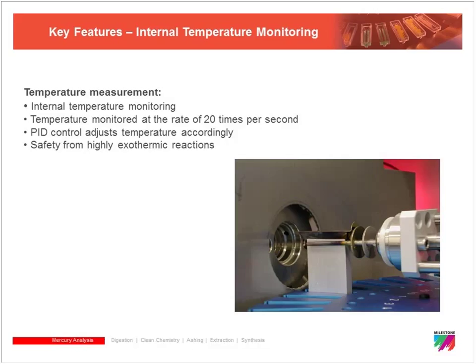So you can predefine this feature prior to your analysis, but generally for the most part you'll only need one or two methods, where you have one method for all of your samples, and then if you are running some very high oil or fat samples, you would have another one that allows you to extend out your heating cycle. This can all be done on the front end through the software, and this PID controller makes sure that the heating cycle sticks to this user-defined heating profile.